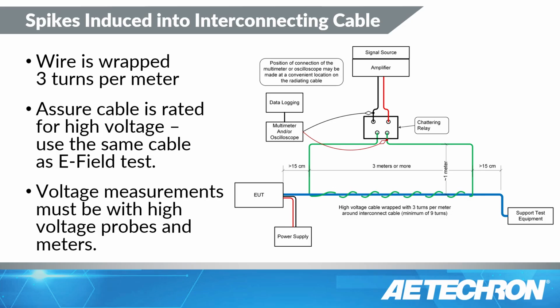And finally, let's talk about the spikes induced in the interconnect cables. We also call this chattering relay. If you notice, we have this wire wrapped around the cable once again. Well, since we're dealing with high voltages on this wire, 600 volts or higher, I recommend just using the exact same cable you had for the previous test. Might as well use that same silicone cable. You've already wrapped it around there. Just drop in the chattering relay test, and you're off and running. This is a standard, normally closed relay.